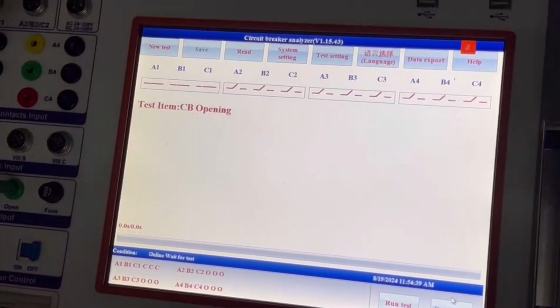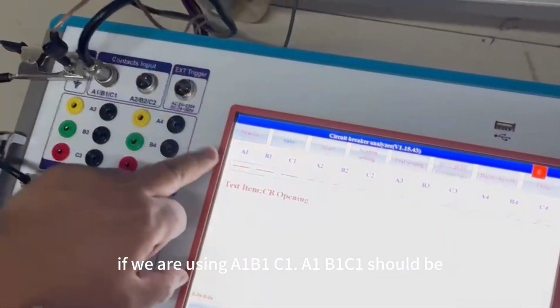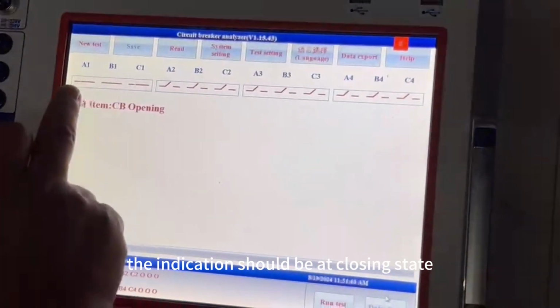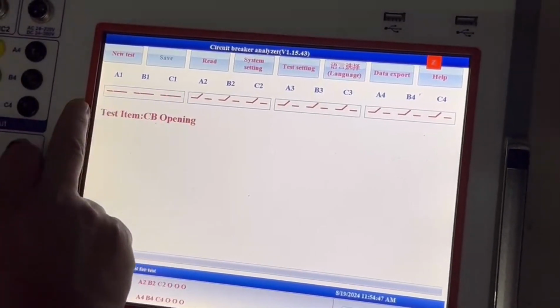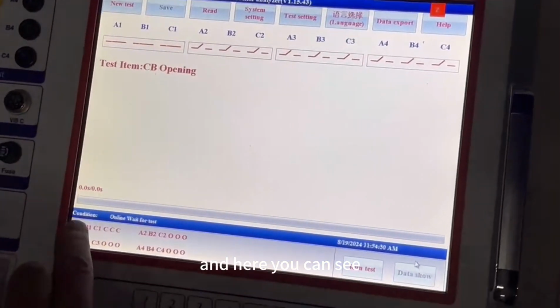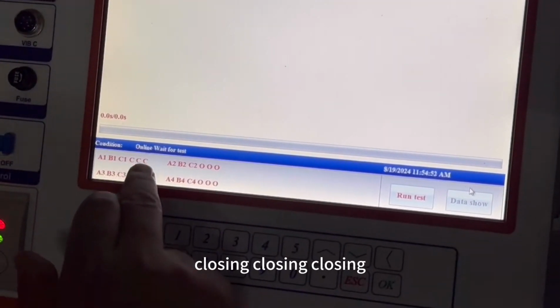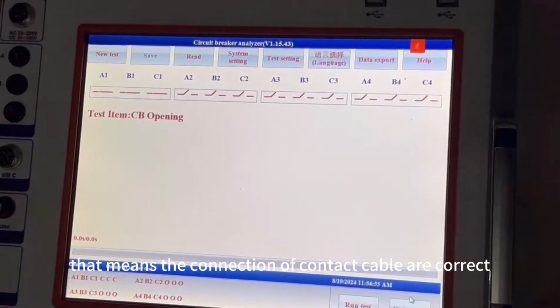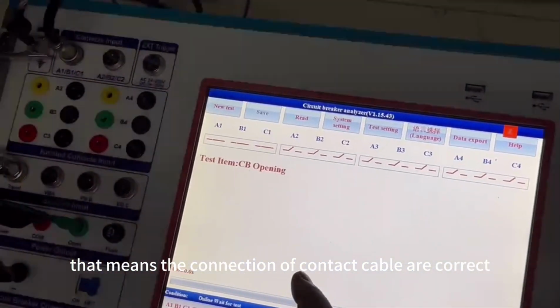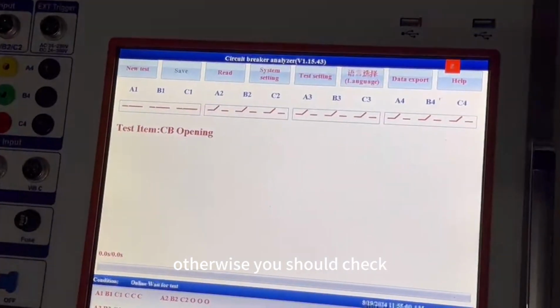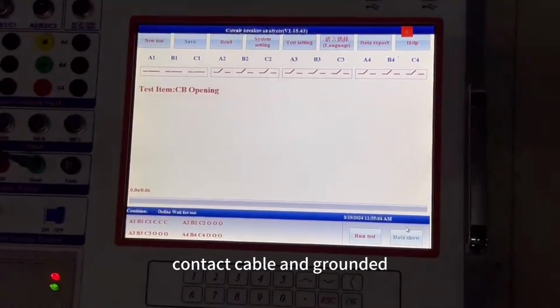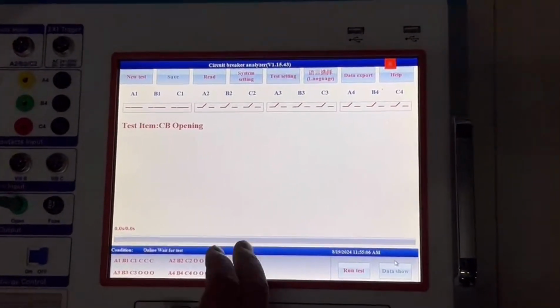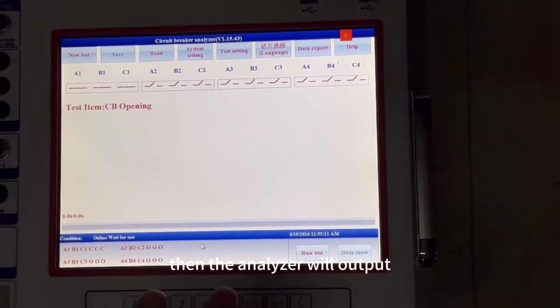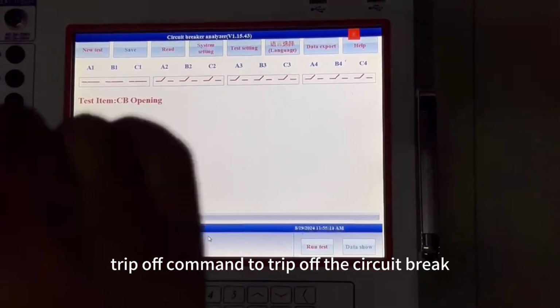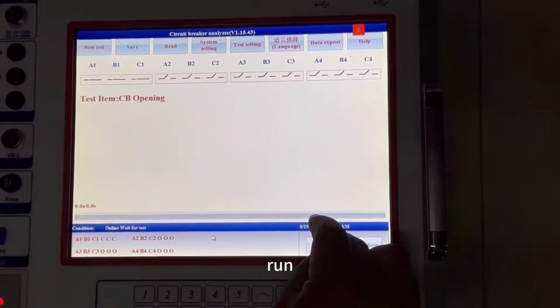So if we are using A1B1C1, the indication should be at closing state. For example, here closing, and here you can see closing, closing, closing. That means the connection of the contact cable is correct. Otherwise, you should check the connection of the contact cable and the grounding. Now we run the test. Then the analyzer will output a trip off command to trip off the circuit breaker. Run.